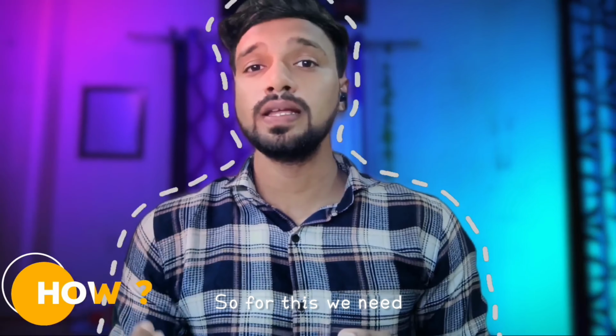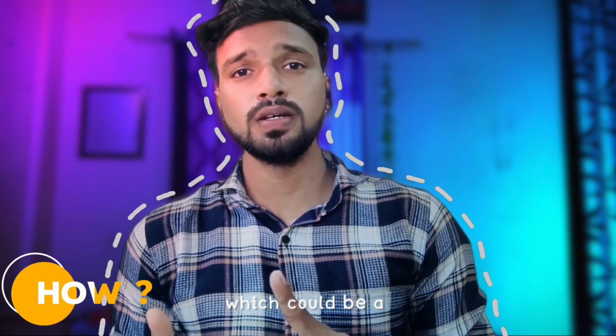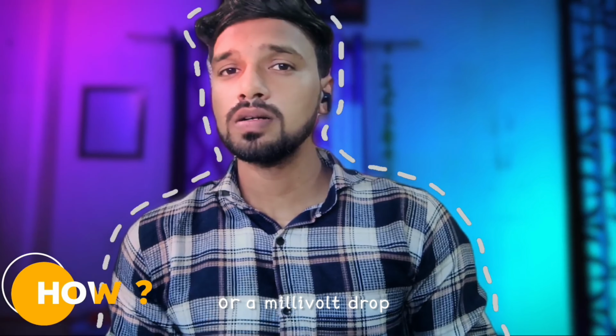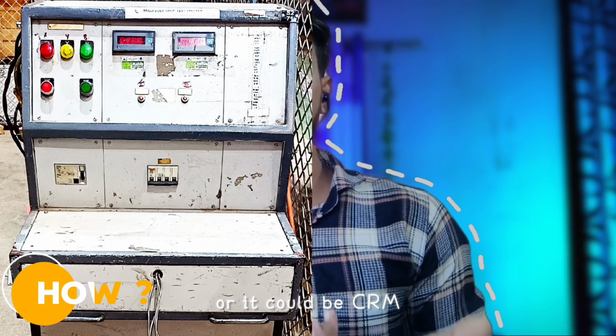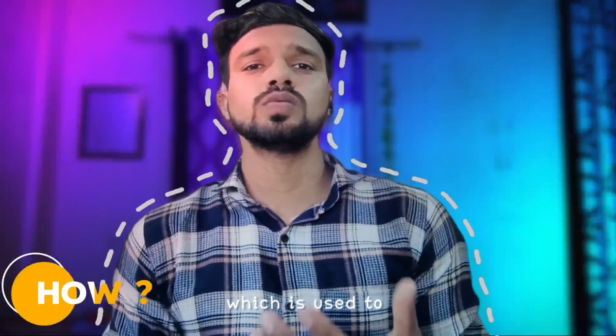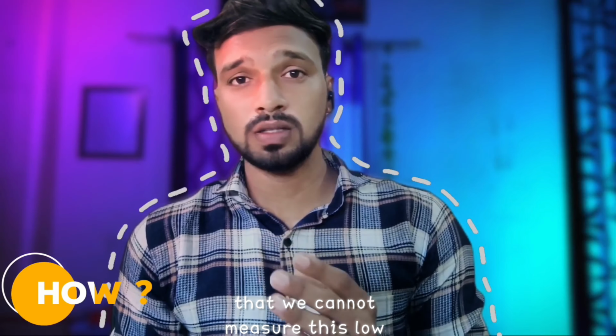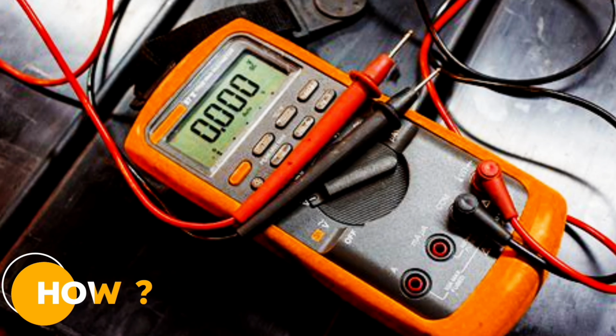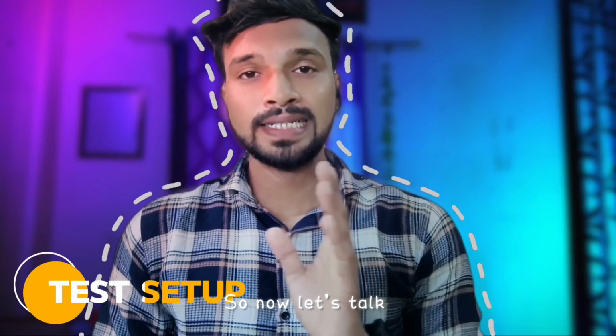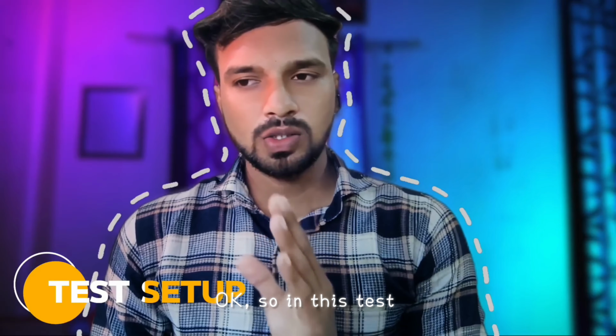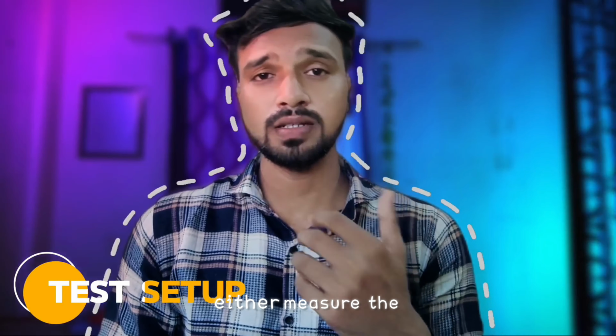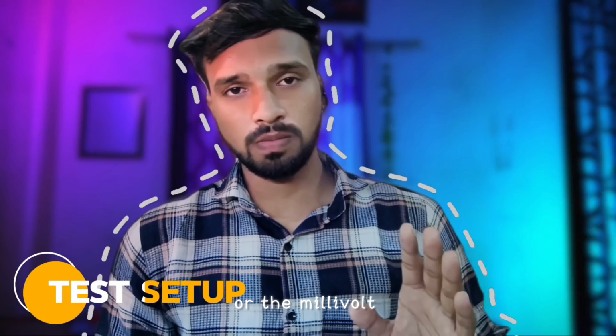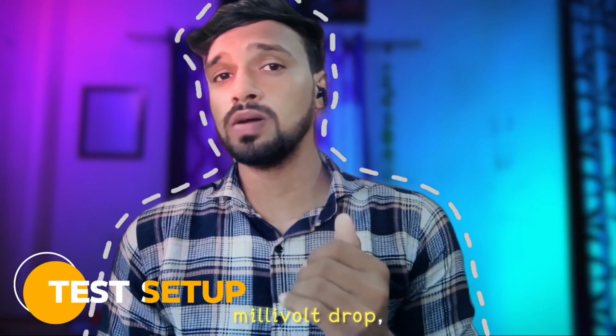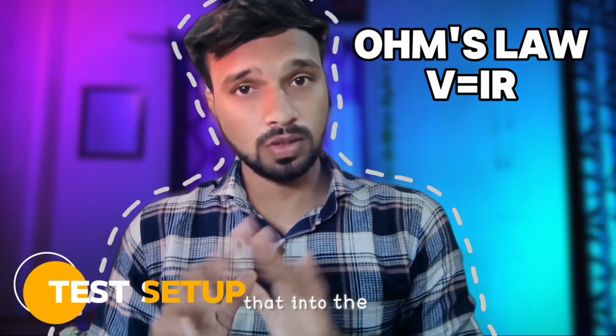Now, let's see how this test is actually done. For this we need a testing trolley, which could be a micro-ohm trolley or a millivolt drop test trolley, or it could be a CRM test kit, which is used to measure the micro-ohm resistance. One more point to remember is that we cannot measure this low resistance with regular multimeters. That is why we need all these tools. So now let's talk about the test setup. In this test we are using a millivolt drop test trolley. As far as I see, we can either measure the contact resistance or the millivolt drop. If we are measuring the millivolt drop, then by using Ohm's law, we can convert that into the contact resistance.